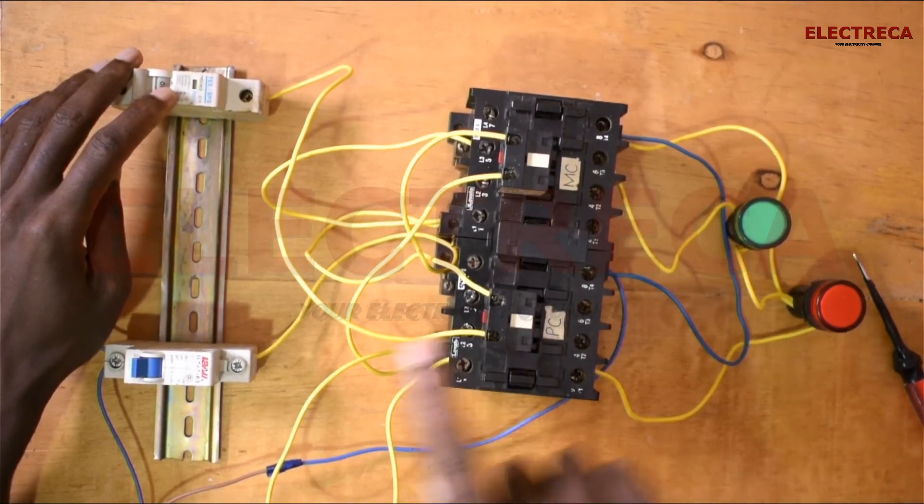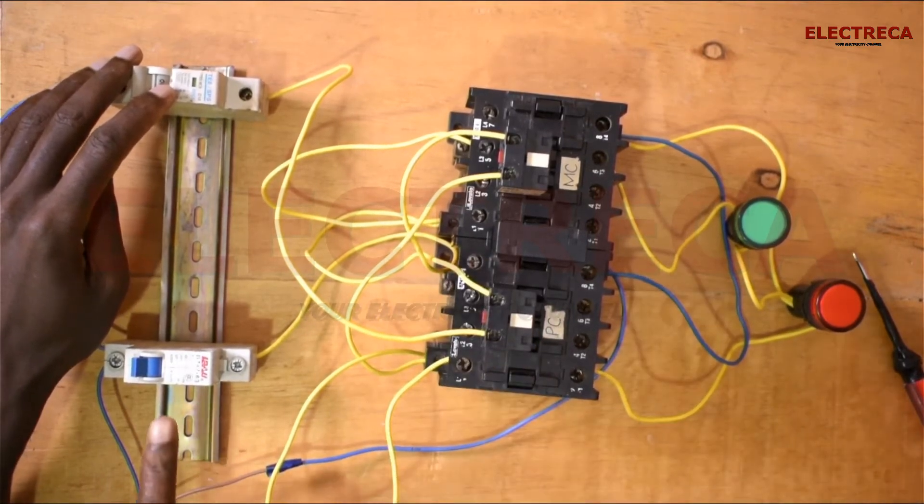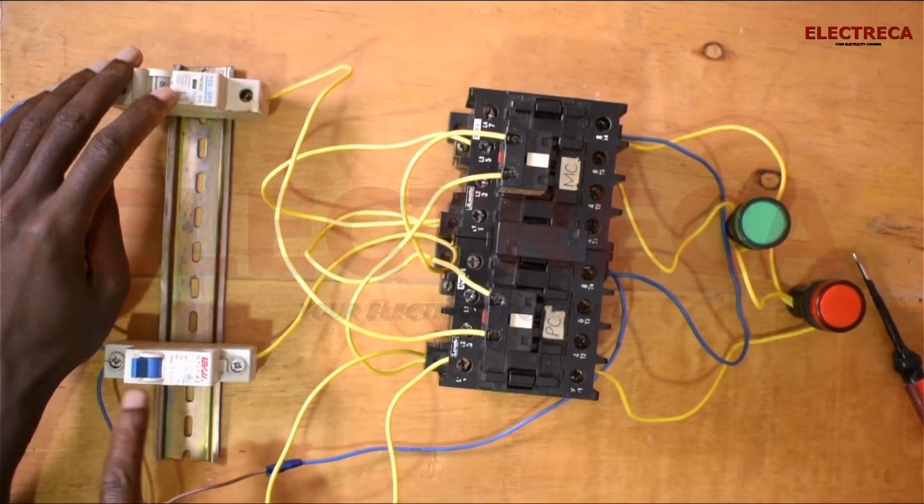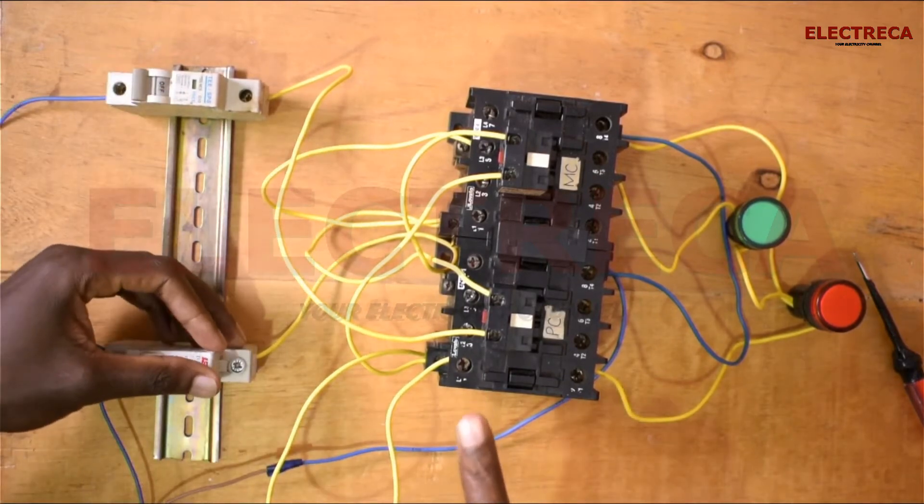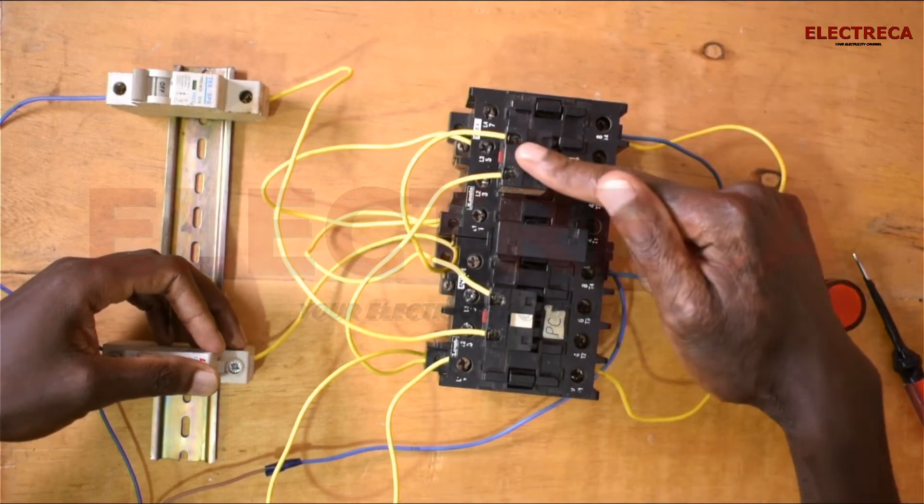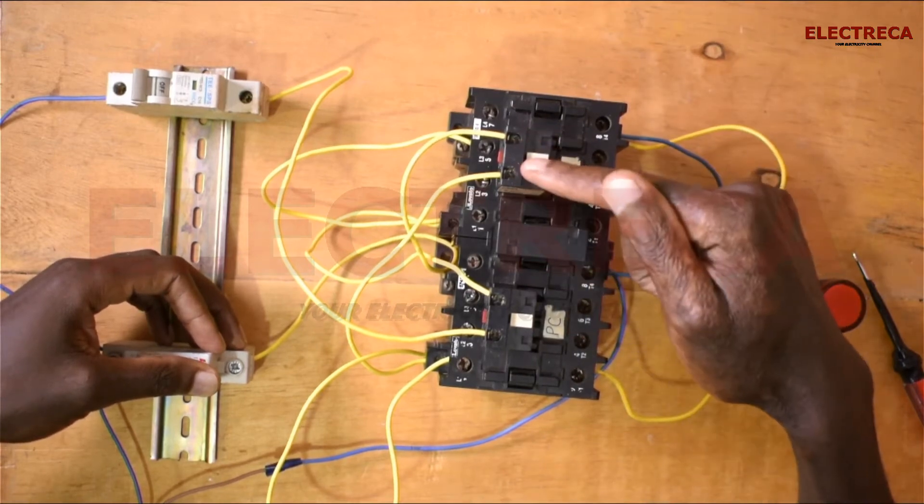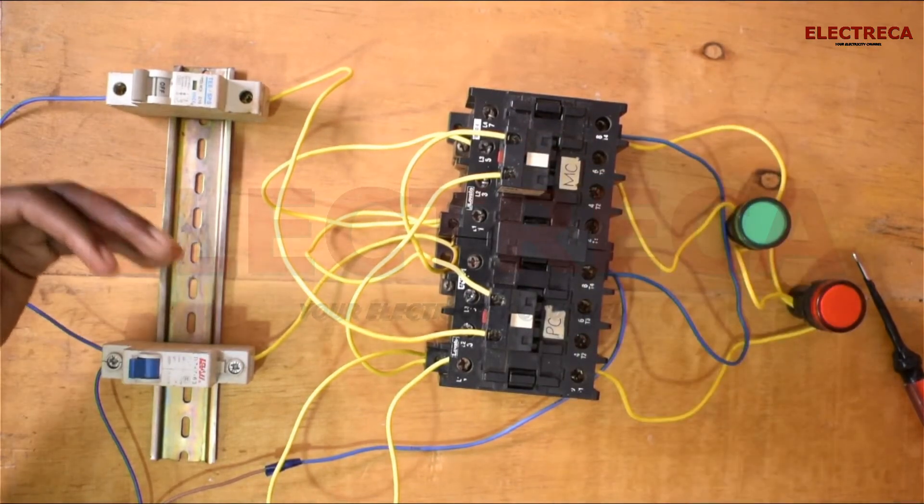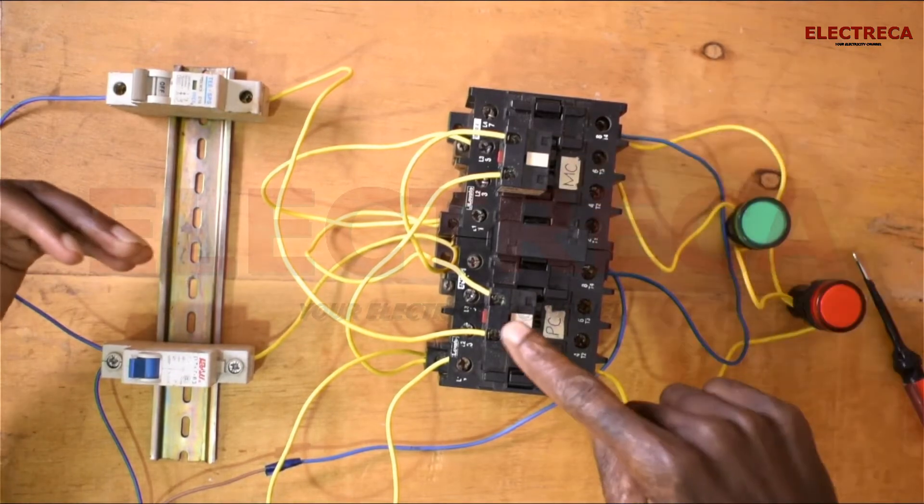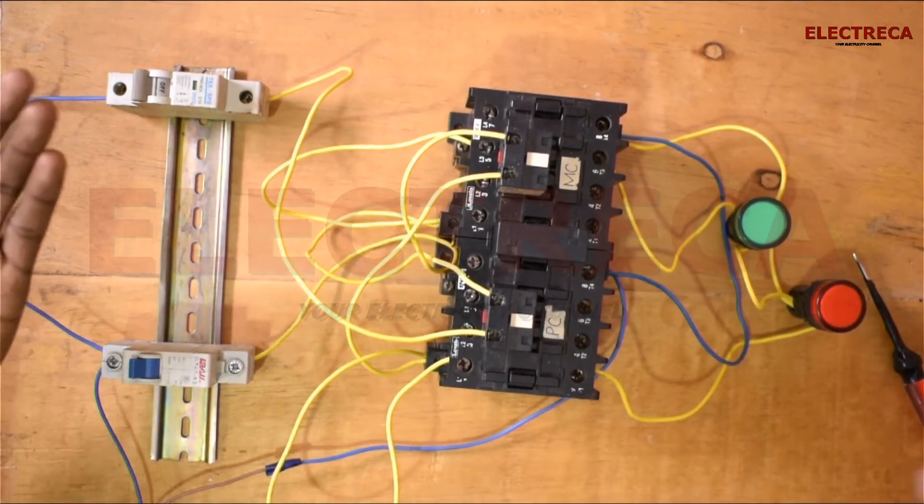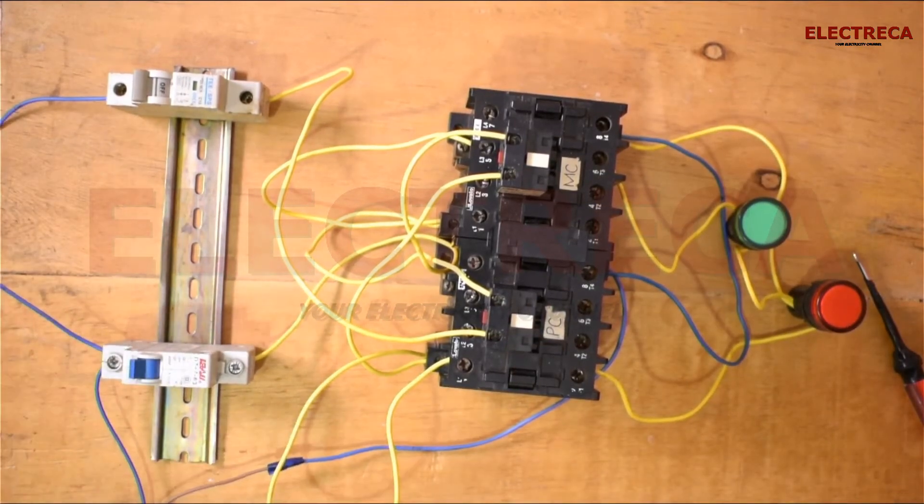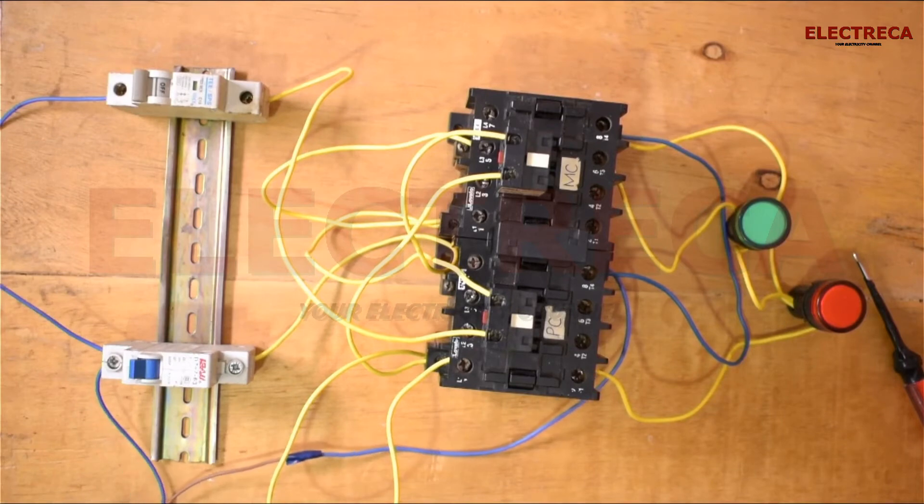Same thing with the generator contactor or the backup contactor. To energize the coil, it has to go through the main contactor, okay? Such that if one contactor is closed, this is closed, this is open, so we won't get any problem. So let's give it a test and we'll see what happens.